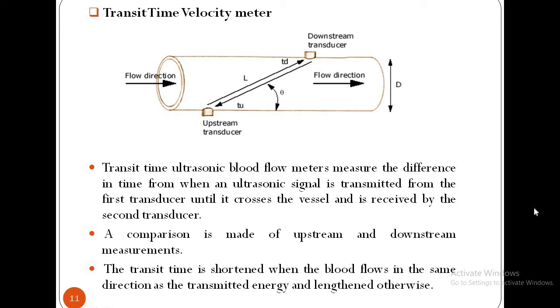Transit time ultrasonic blood flow meters measure the difference in time when an ultrasonic signal is transmitted from the first transducer until it crosses the vessels and is received by the second transducer. A comparison is made of upstream and downstream measurements. The transit time is shortened when the blood flows in the same direction as the transmitted energy and lengthened otherwise.